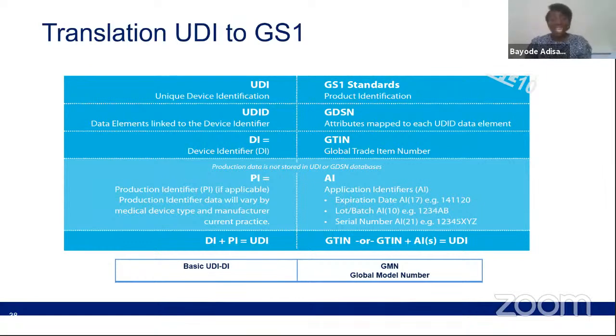This slide translates how the GS1 standard meets UDI requirements. You can see that the UDI-DI solution in the GS1 standard is a global trade item number. Production identifiers in the GS1 standard are referred to as application identifiers. You've probably seen a barcode on the bottom of a device with several prefixes and numbers after them. For example, for a lot number, the prefix 10 would be included in brackets and the lot number would follow. As I said, DI plus PI equals UDI, and in the GS1 standard it's a GTIN plus the application identifiers equals the UDI. GS1 have also created a solution for the basic UDI-DI, and that's the global model number.